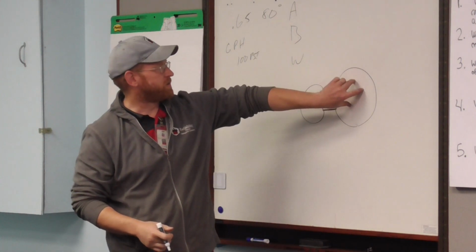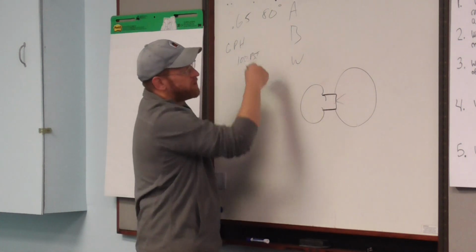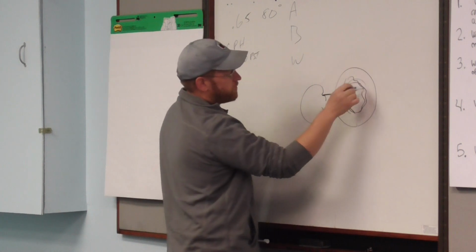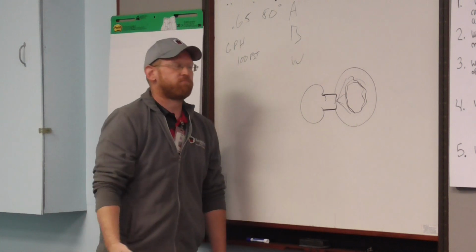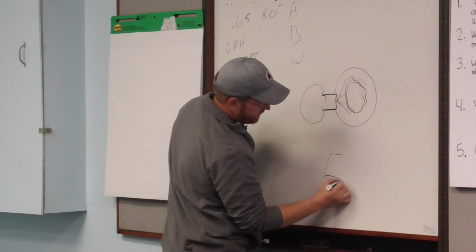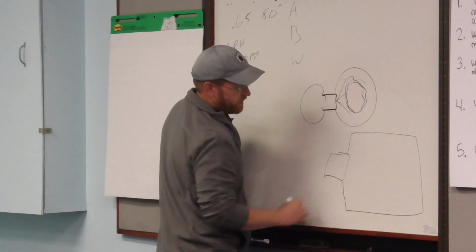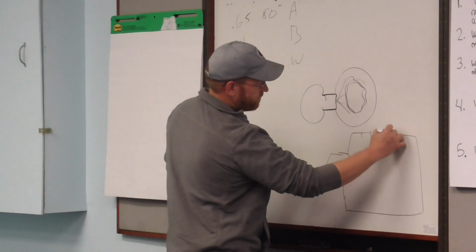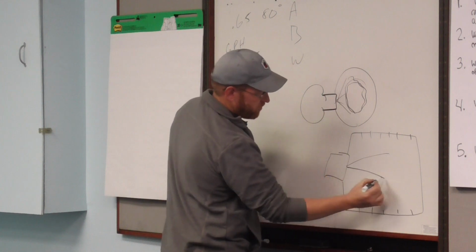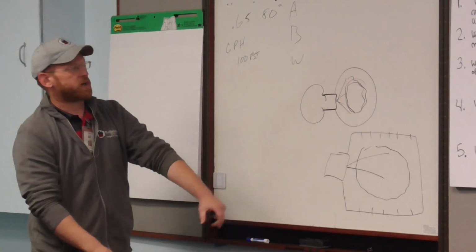If you have a small round combustion chamber, like the big oil drum furnaces, they're gonna want it with a wide spray angle. So it's gonna spray out that way to fill this part in with flame. If you have something like a bigger boiler, a multi-plate boiler, a 6-plate boiler or some giant long thing, it's gonna go straight in there. Then you're gonna want a more narrow angle, so it'll fill it in a longer spray.